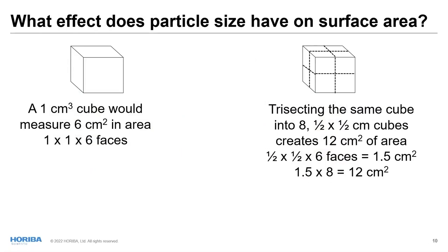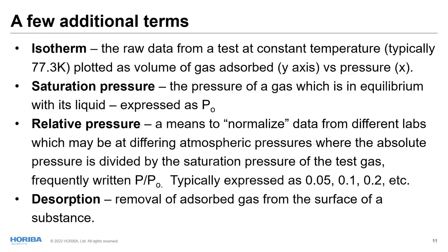What effect does particle size have on surface area? Imagine a non-porous cube one centimeter on edge — it measures 6 square centimeters. Trisecting it into eight half-centimeter cubes creates 12 square centimeters of area. Trisecting those into quarter-centimeter cubes doubles it again to 24 square centimeters. As particle size decreases, surface area increases quite substantially. The isotherm is the raw data from a test at constant temperature — typically 77.3 K for liquid nitrogen — plotted as volume of gas adsorbed on the y-axis versus pressure on the x-axis.